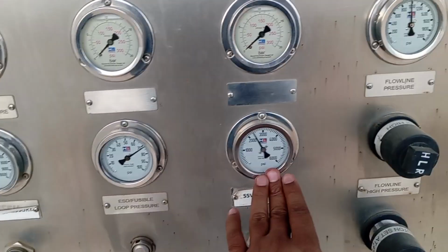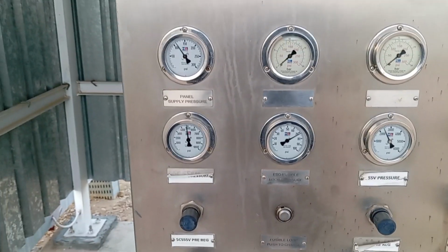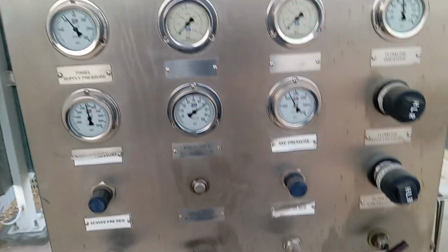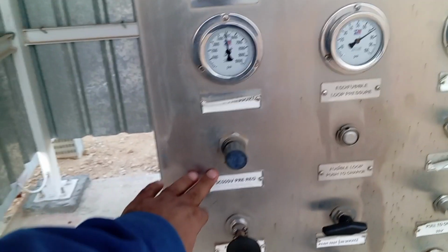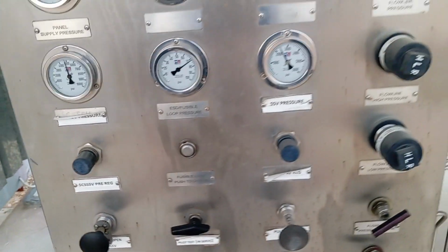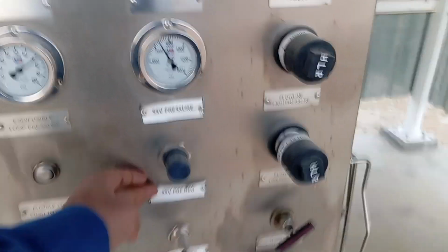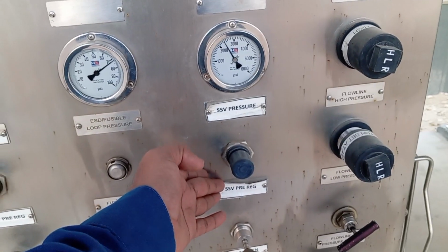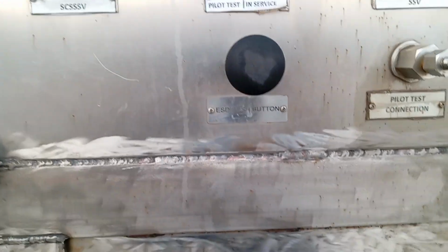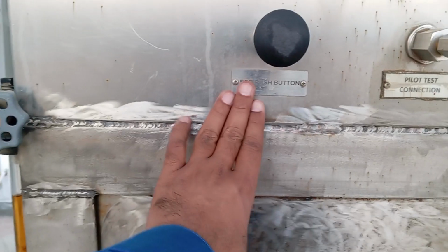In this wellhead control panel, both double SV and triple SV are hydraulic. In some cases, we have a pneumatic double SV, but the triple SV must be hydraulic. And then we have a regulator for the adjustment of our triple SV pressure. Through this regulator we adjust the triple SV pressure, and then we have a double SV regulator, and through this regulator we adjust the double SV pressure according to our requirement. As I mentioned earlier, the same loop is used for the ESD and the fusible loop. And here we have an ESDV valve. In case of an emergency, the operator can shut the wellhead control panel through this ESD valve.